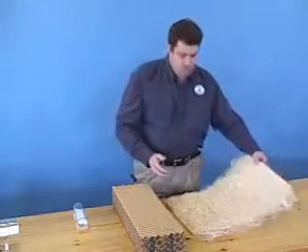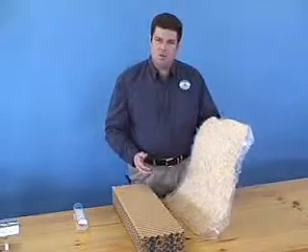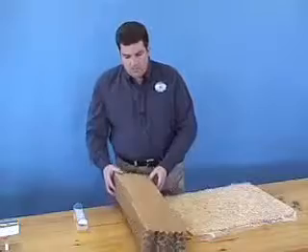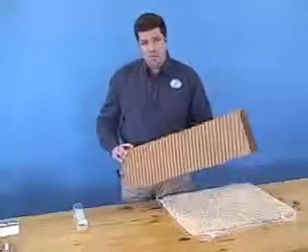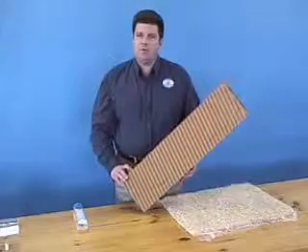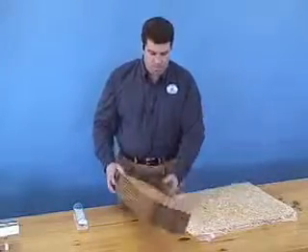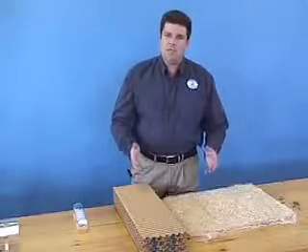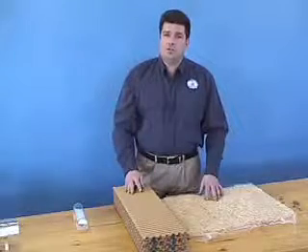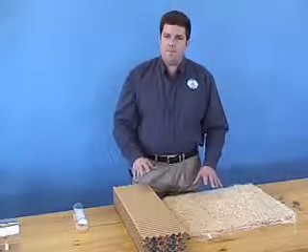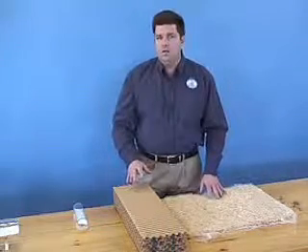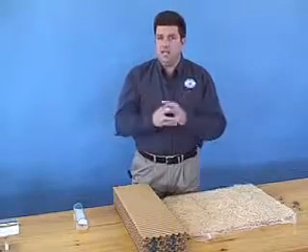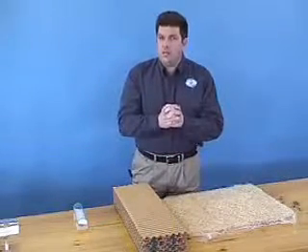Aspen pad swamp coolers can reach to about 70% of the wet bulb temperature from their starting point. Corrugated cardboard type swamp coolers are better at swamping the air, and they can reach to about 90% of the wet bulb temperature. These types of mechanisms are called direct evaporative coolers because they add moisture directly to the air that enters the building. Direct evaporative cooling is adiabatic cooling, which means no heat energy is removed from the airstream. The heat is simply hidden in the water molecule in the air.